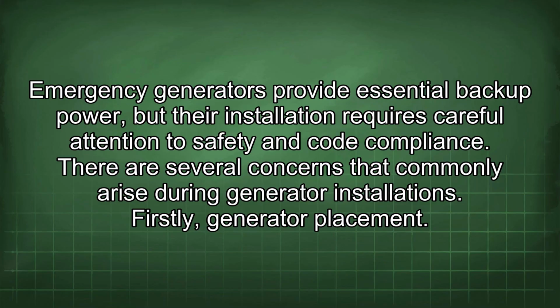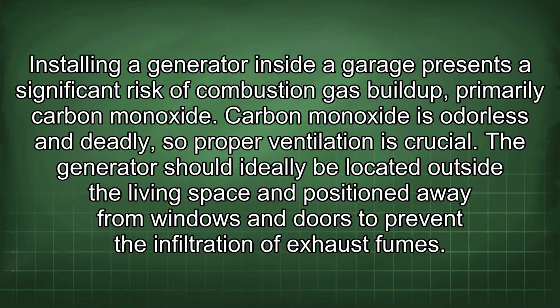Emergency generators provide essential backup power, but their installation requires careful attention to safety and code compliance. There are several concerns that commonly arise during generator installations. Firstly, generator placement. Installing a generator inside a garage presents a significant risk of combustion gas buildup, primarily carbon monoxide. Carbon monoxide is odorless and deadly, so proper ventilation is crucial.